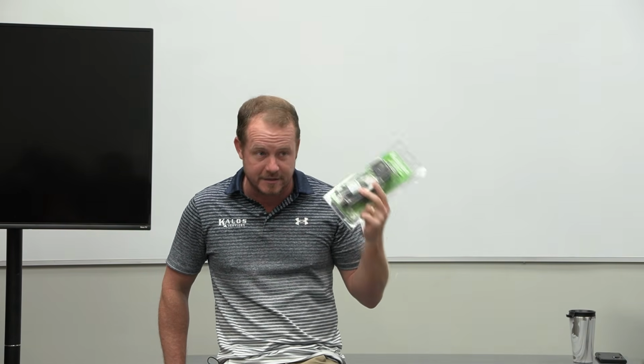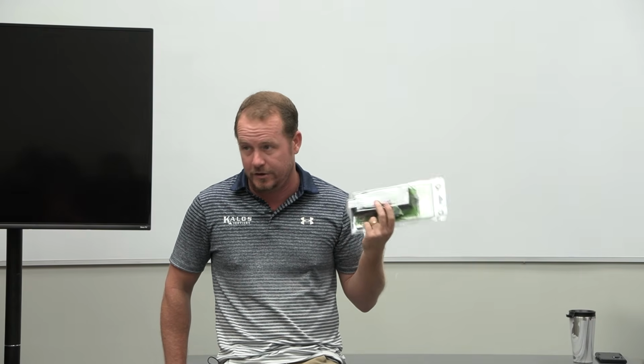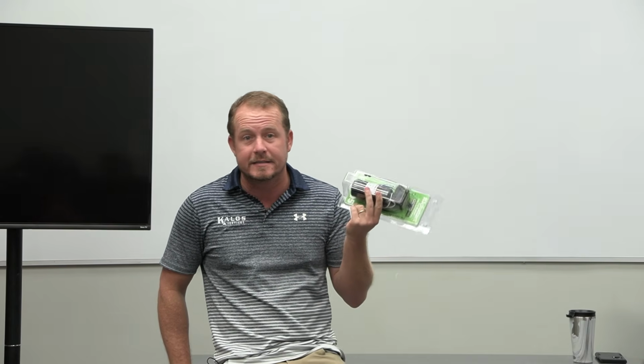You're not going to leave somebody without air just because you want to be all dogmatic about not using an aftermarket hard start kit. Now, let's say that it is a new system and you put this on there and it does start running. Now what are you going to do? Well, in this example, it's a unit that's under warranty. We installed it, right? 3 months old, something like that. You're going to want to look at why. Why did this need this?